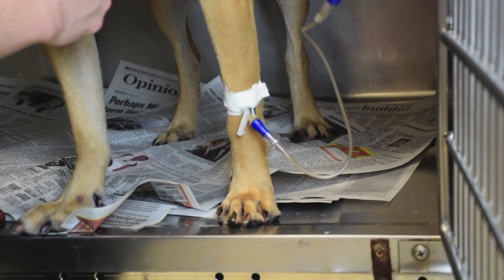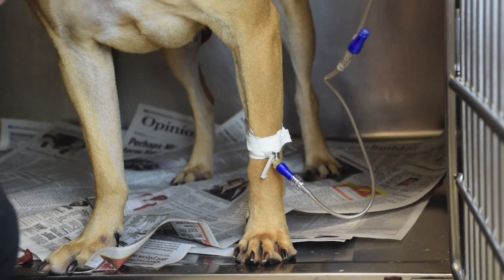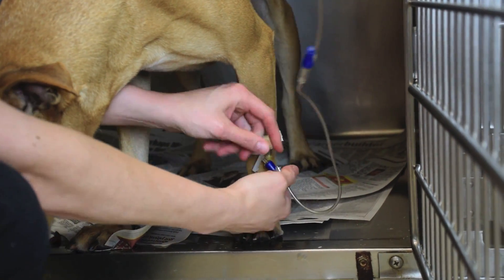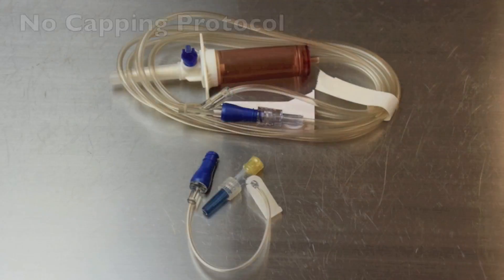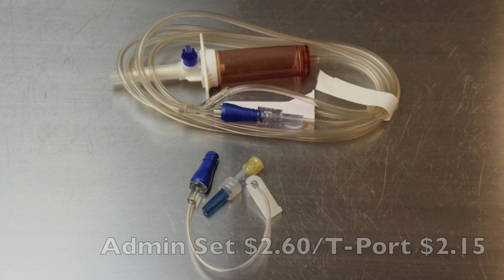The microclave is a closed system that immediately closes after disconnect and does not get capped for patient walks. The patient end of the IV line is then Luer-locked onto the swabbable MicroClave Y-site to protect the exposed end. We call this combination our no-capping protocol that saves the hospital money, the technician time, and protects the patient from catheter-related bloodstream infections.